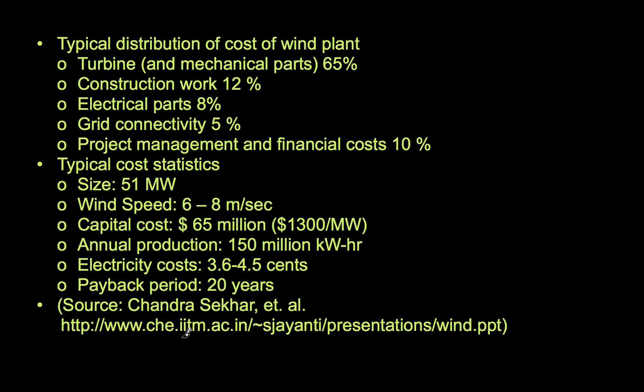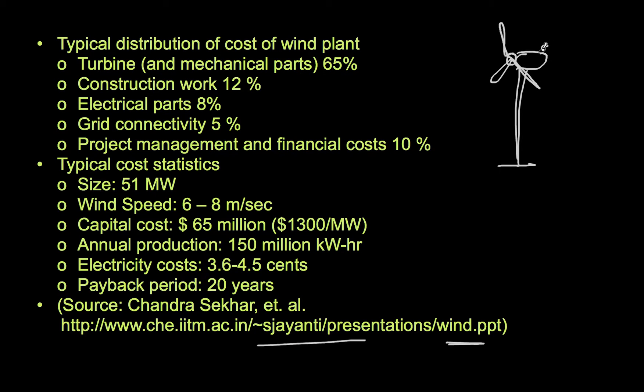Looking at the typical distribution of costs in a wind plant: the turbine itself accounts for 65% of the cost, construction is 12%, electrical parts are 8%, grid connection is 5%, and the remaining 10% covers project management, financial costs, salaries, and similar expenses. This is the general cost distribution for a wind plant.